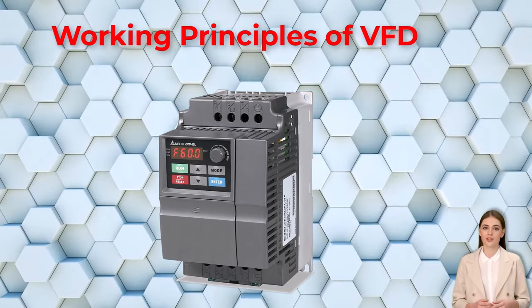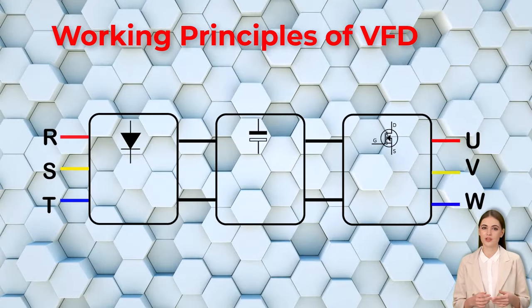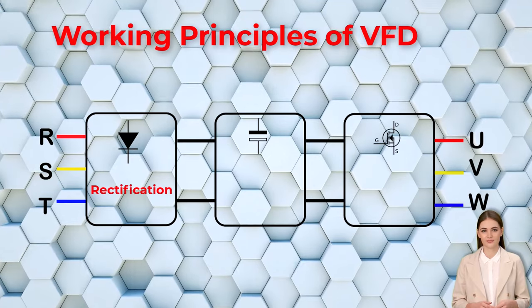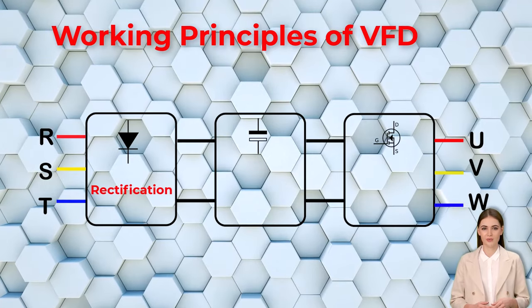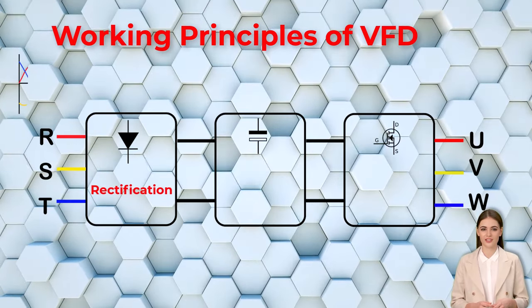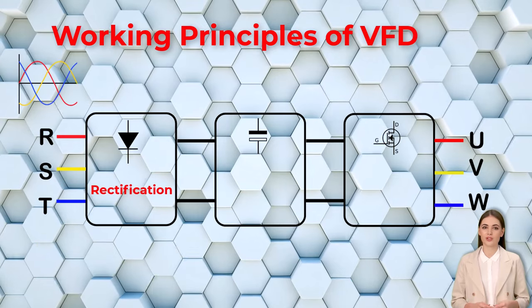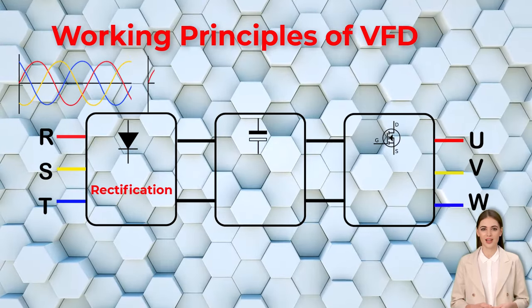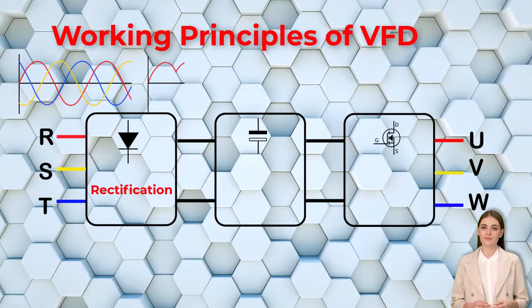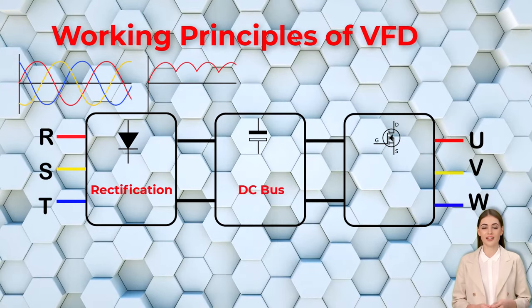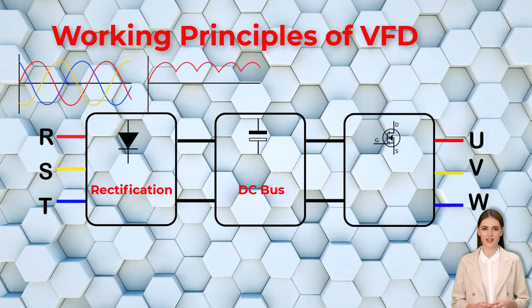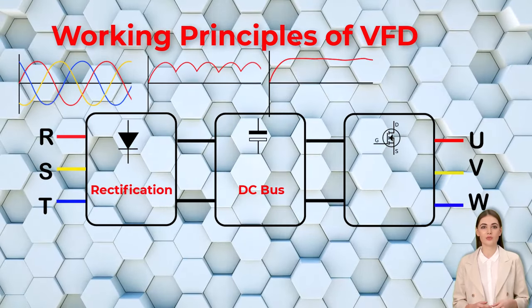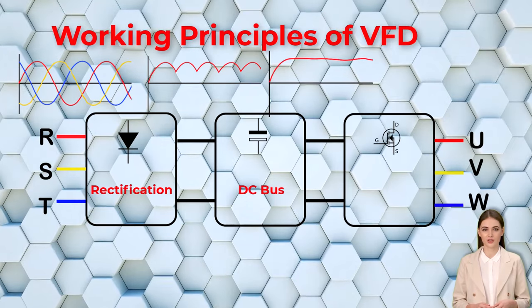The core of a VFD is its ability to manipulate the frequency and voltage of the AC power supply to the motor. This involves a three-stage process. First is rectification: incoming AC power is rectified into DC power using diodes or thyristors, converting the alternating current into direct current. Second is the DC bus: the rectified DC power is stored in a DC bus capacitor, smoothing out any ripples and providing a stable DC voltage source.